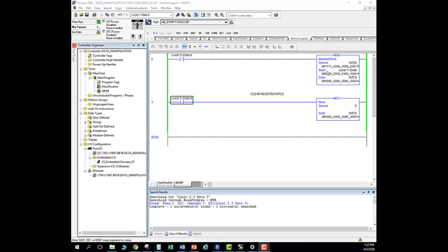So when I come back through here and I create one of these inputs and turn them on, that will be aligned with something like this, see, I turn on bit number 16. So I got this guy on here. When I trigger this guy here, it will come to be true down here. Awesome, excellent. So now you can see that the mask only allows where there's a 1 through to the next segment here, into this integer 1.